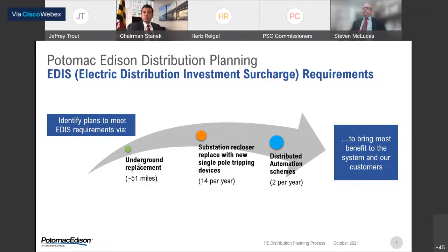It's something we put into place, operational through next year under its current approval. In that program, we replace about 51 miles of underground cable a year because of the concentric neutral from back in the 70s, when Maryland started putting new services and extensions underground. That underground was bare concentric neutral at the time, and much of it is reaching the end of its useful life. So we're proactively trying to identify priorities for replacing that cable from a customer satisfaction perspective, and we've done very well in that regard, I believe.